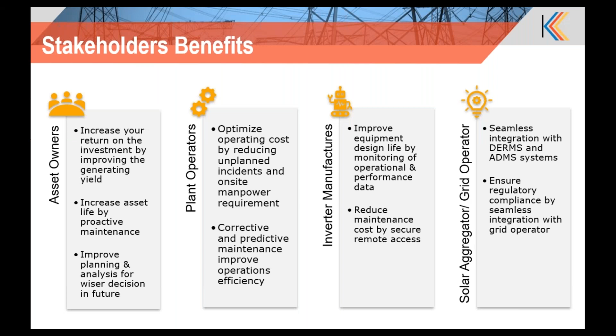I'll go to the architecture. This solution doesn't give a detailed picture of the data exchange with the utility system. Kalki.io can exchange data with utility systems like the EMS system or the DERMS through standard telemetry interfaces. It supports utility standard interfaces like DNP3, IEC 60870-104 or 101. It also has support for ICCP, that is Inter Control Center Protocol. Usually we've integrated with EMS systems using these three sets of protocols.